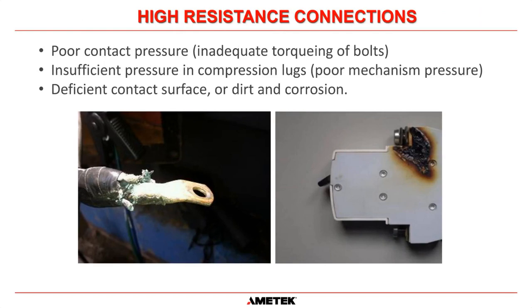Well, the first one is high resistance connections. It could be insufficient pressure in a compression lug. In other words, it hasn't been crimped correctly. It could be that the contact surface has dirt or corrosion. You can see here that's starting to corrode a little bit. And if that got onto this surface area here, that would cause a high resistance connection.